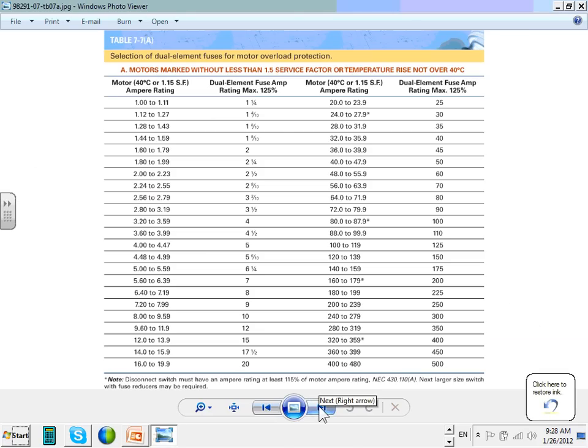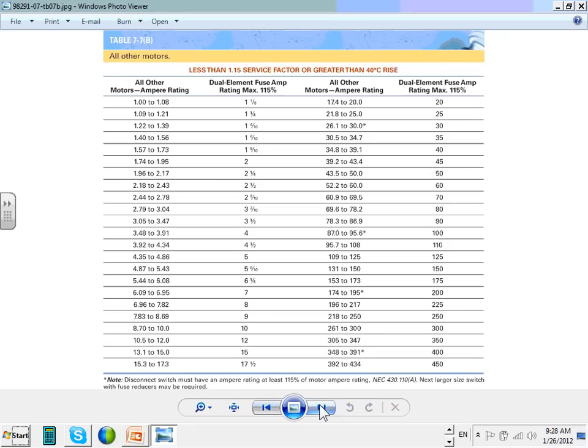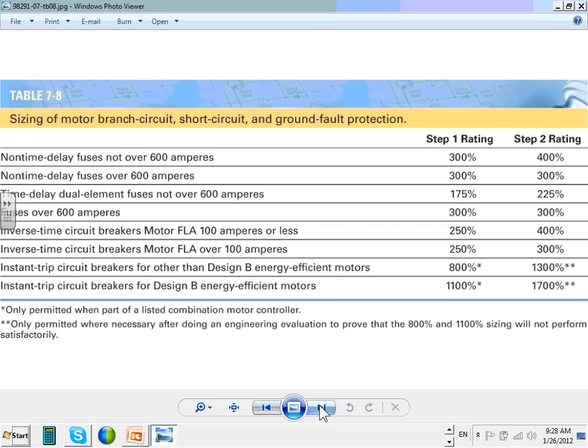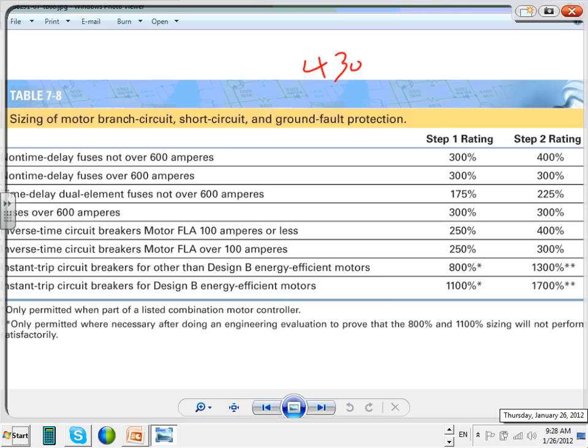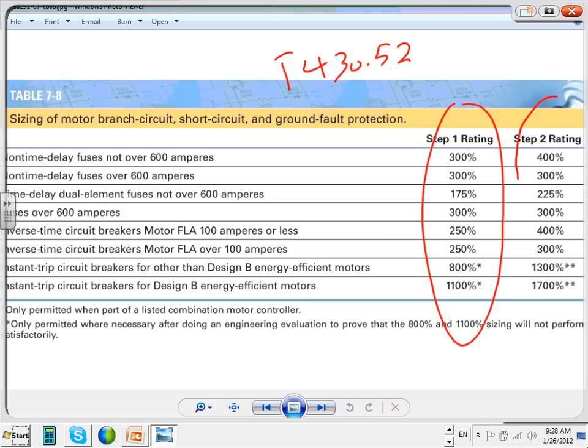This is a couple of service factor ratings for dual element fuses, guys. You can use them as a guide. Dual element time delay fuses, we have them in the book. This is the multiplier, this is your Article 430.52 table. You guys are very familiar with this. Here's your normal size, that's what you're going to size for. If you size based on 300% but the motor keeps tripping, the code allows you to go higher, but after you have proven that it doesn't work. So as designers, Nick, how are you going to prove it when you haven't designed it yet? So where's your default? Right here. We default right here. It is only under extreme conditions that you can go higher than that, and these are all exceptions.